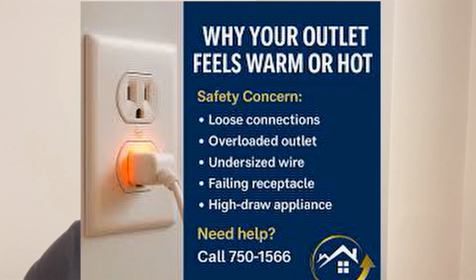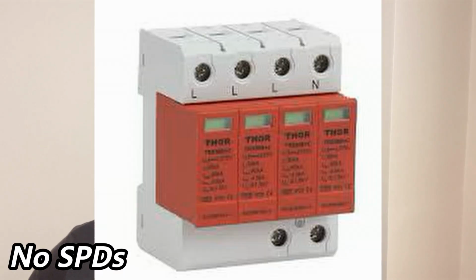Many fires can start inside the consumer unit, not necessarily at the appliance, or inside the distribution. When I say consumer unit, it's interchangeable with distribution board. Defect number 3, no arc fault or surge protection devices. Most new homes in Ghana will have MCBs, hopefully you will have the RCD, but typically they will not have a surge protective device and definitely not have arc fault protection either.